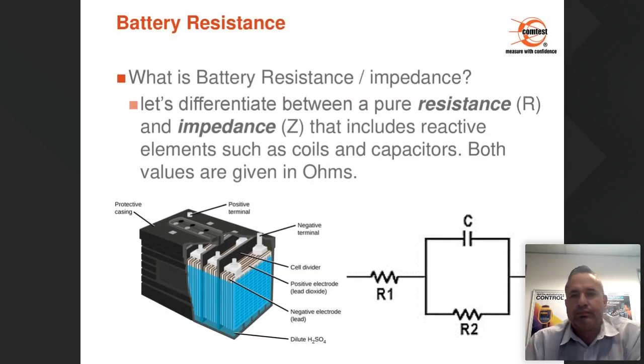Battery resistance. So when do we have to measure your battery system? IEEE recommended maintenance procedures are as follows. For your flooded batteries, we need to test the total voltage of your system monthly, the charger output current and voltage, ambient temperature and ventilation, and visual inspection. Visual inspection is always a good way to also see what is happening in the installation. Electrolyte levels, so that would be the acid inside the batteries, we need to check. Pilot cell voltage and specific gravity. And then quarterly, we need to check your specific gravity, the individual cell voltage, and then cell temperature.